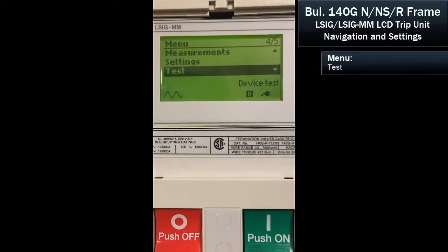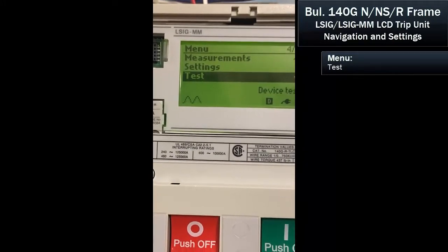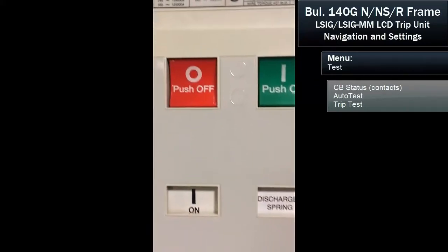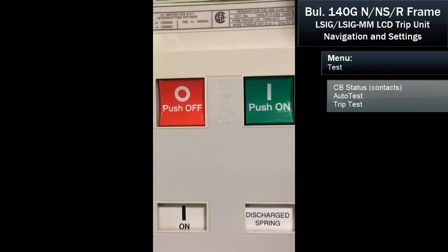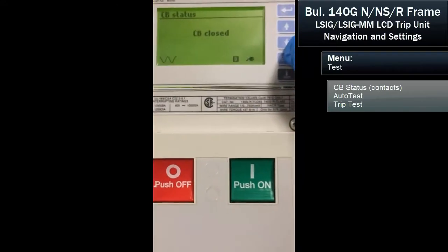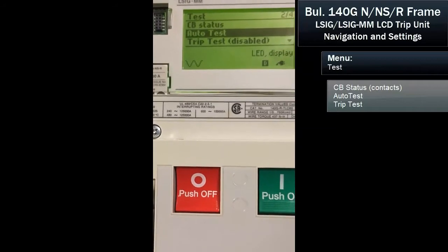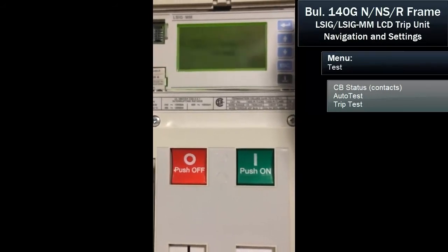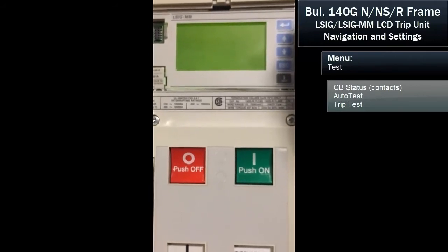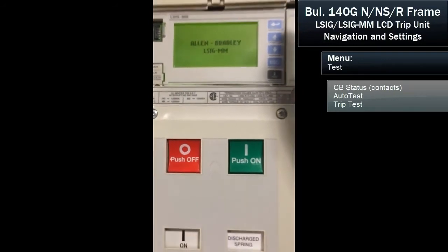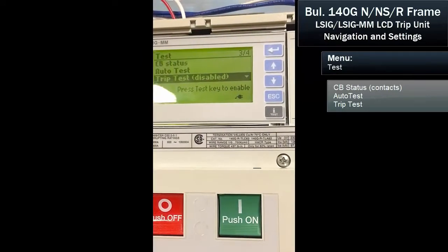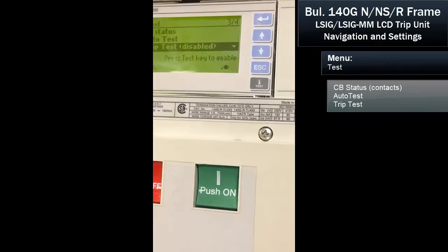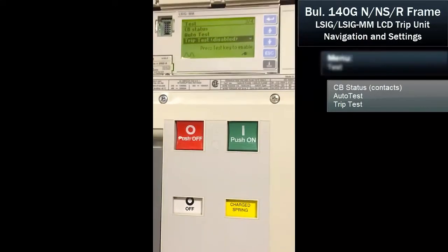The breaker also has a test function. We can see the status, and while we were away, I did turn the breaker on using the push button. We can run an auto test where the trip unit itself runs through diagnostics. We also have a trip test where we can actually trip the circuit breaker from the menu — though I don't know how many people would do this in operation.